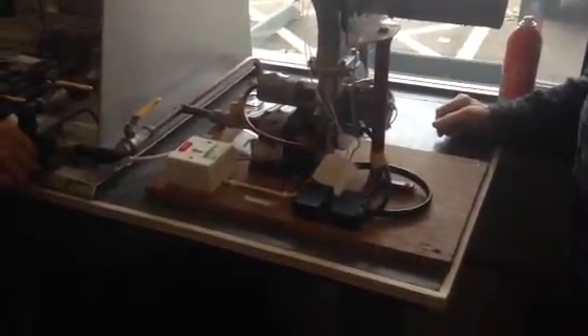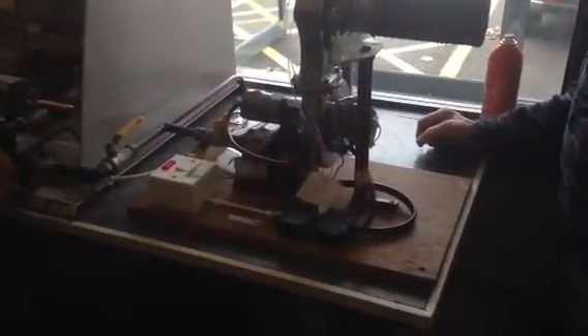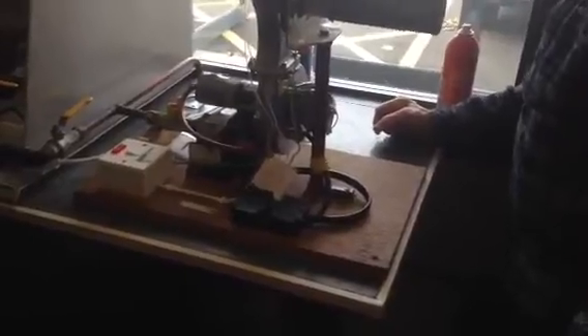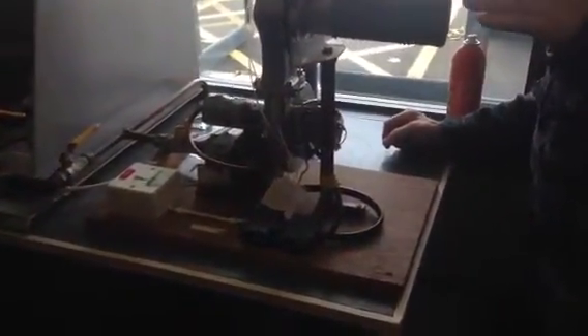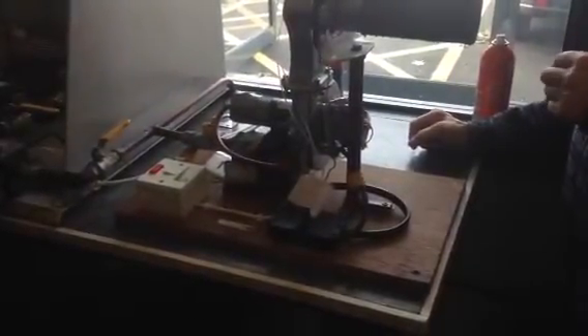It might be a break in the mains, it might be someone's interfered with the mains, they've done work on the gas, whatever, and they've interrupted the supply. But as long as it stays interrupted, it's going to stay off. So it's instant, it's within a second. It doesn't have to cool down. As soon as that flame's not there, that signal shorts directly back as an AC current to the PCB. So it acts instantly.